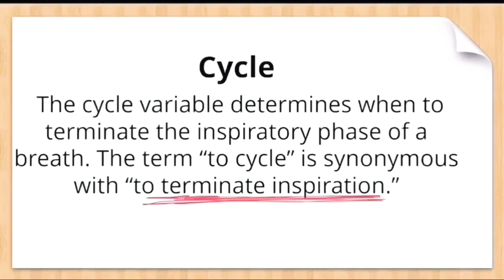The variables most commonly used for cycle include volume, time, and flow. It could be volume cycled, flow cycled, or time cycled. Now in case of volume cycled breath, the inspiratory phase continues until a set volume has been delivered. For time cycled breath, the inspiratory phase continues until a set time has elapsed. For flow cycled breath, the inspiratory phase continues until the inspiratory flow diminishes to a set value.